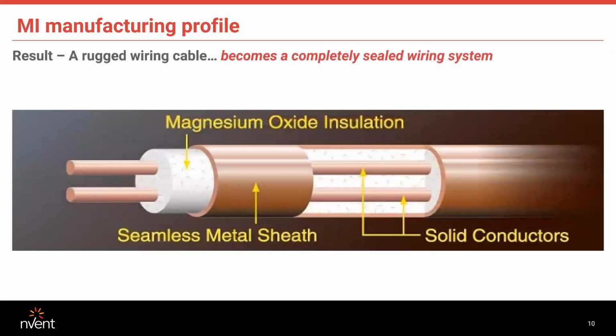And when you're done, you've got a very rugged electrical cable system: magnesium oxide, your copper conductors, and your copper sheath. And it's a product that's inherently resistant to high temperatures. As I mentioned, magnesium oxide is stable up to 5,000 degrees, and the melting point of copper is 1981 degrees. So again, it's inherently resistant to high temperatures.